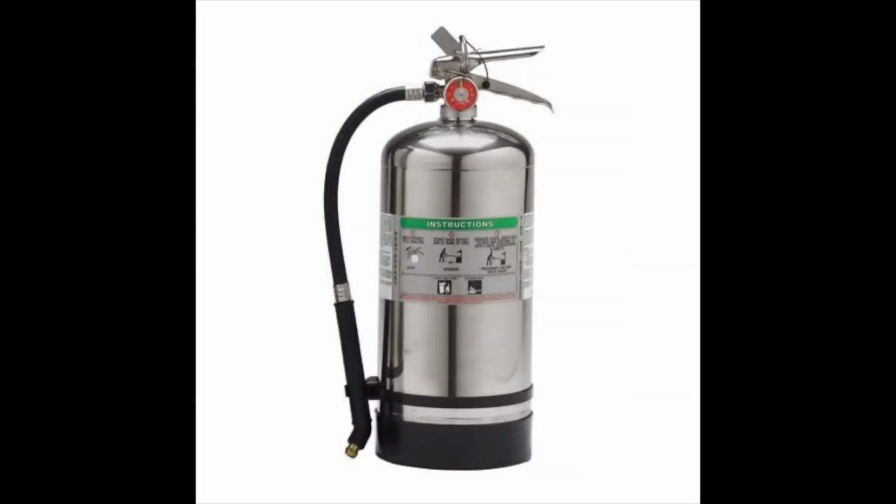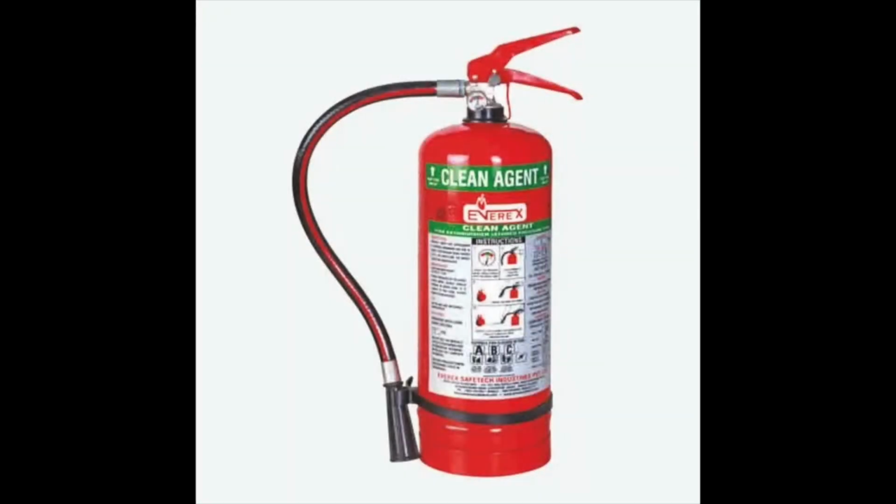Wet chemical fire extinguishers remove heat from the tetrahedron and also prevent reignition by implementing a barrier between the oxygen and the fuel elements. These are commonly used to extinguish grease fires in commercial kitchens. You use these on Class K and A fires. Clean agent or halogenated extinguishers work by interrupting the chemical reaction of the fire tetrahedron. Use these on Class B and C fires.